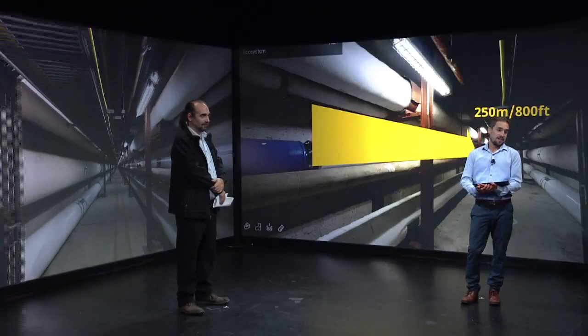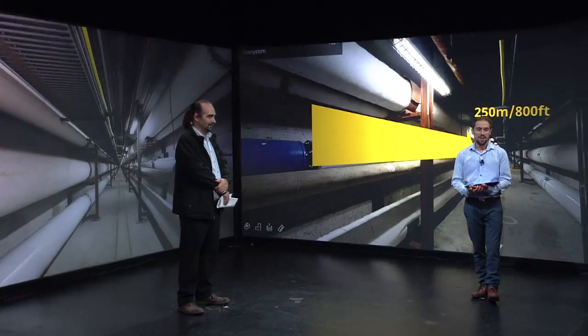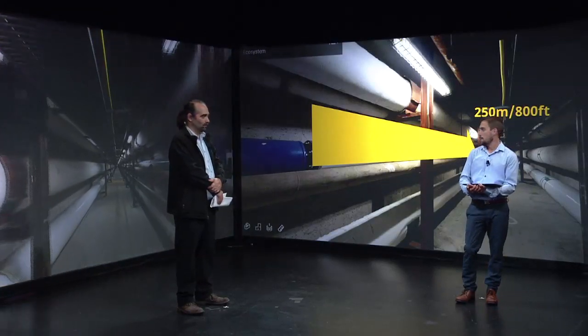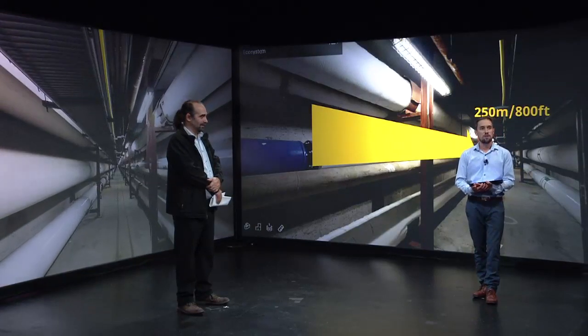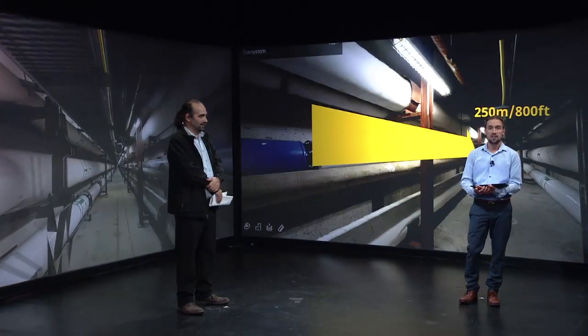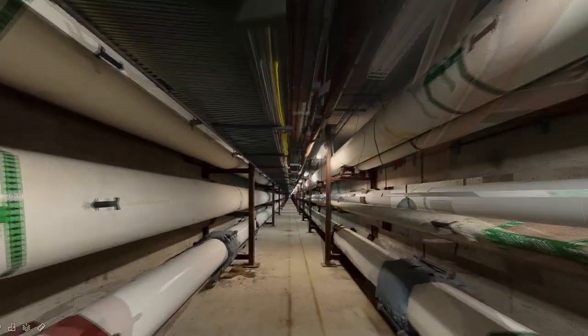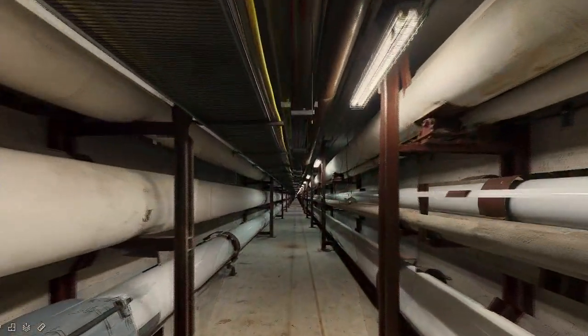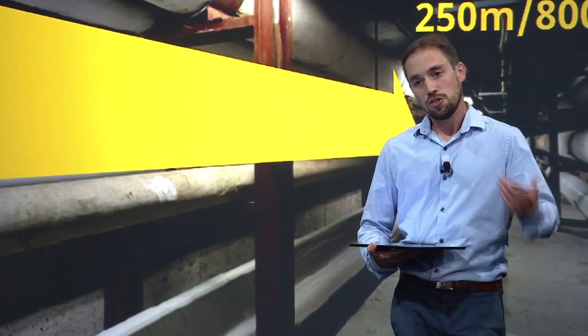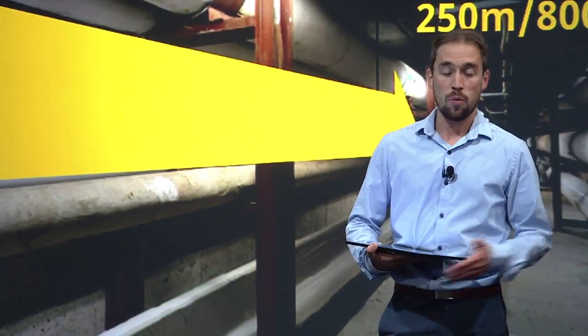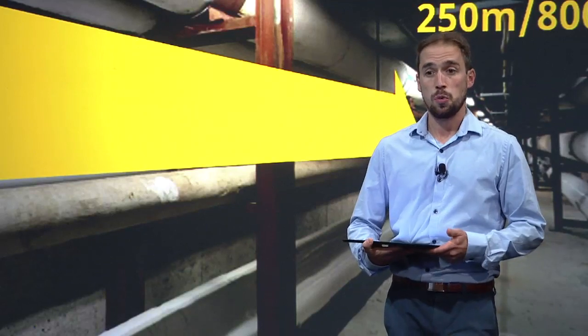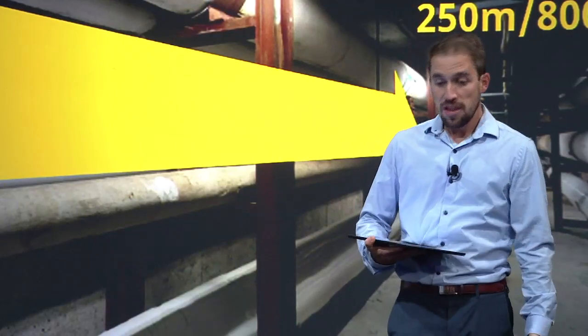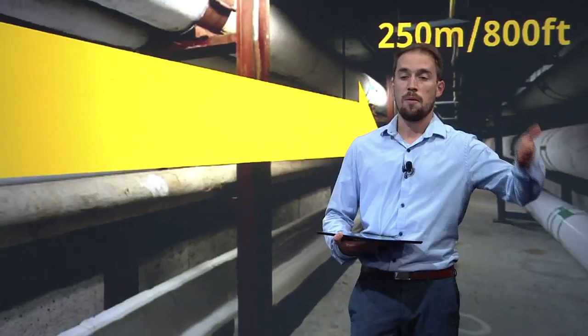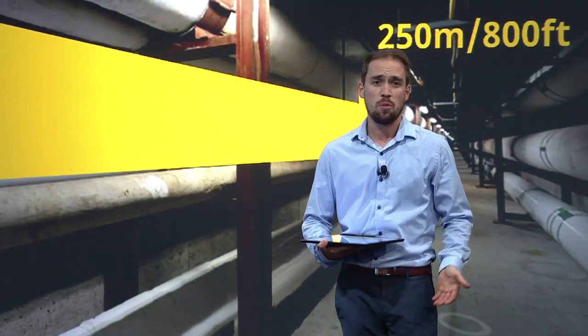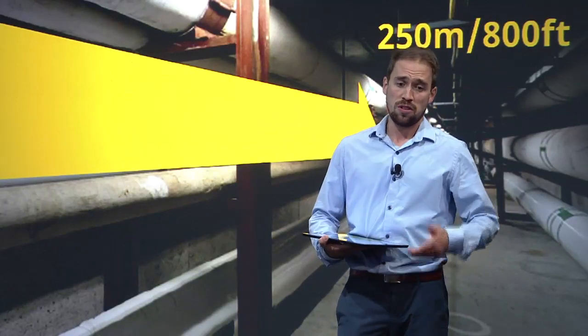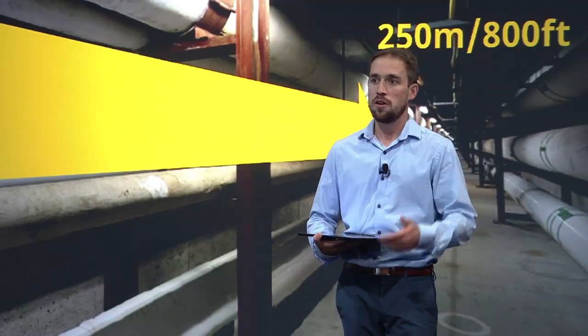In the end, the client was right. When we did the startup, the pipe wasn't too small, but because of the roughness, it was actually the only condensate piping we were trying to reuse, and the roughness was too significant, causing too much pressure drop and not enough flow rate. So we decided to replace it. From the day we decided to replace it to the day it was finished installing, it was less than 10 days—it took less time to install than the time we spent arguing about it.